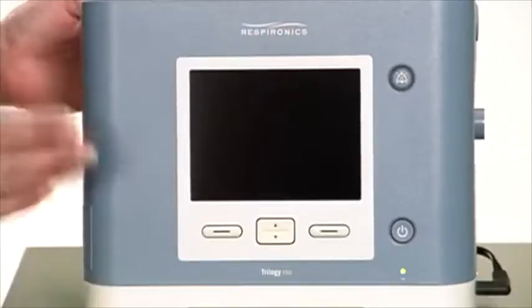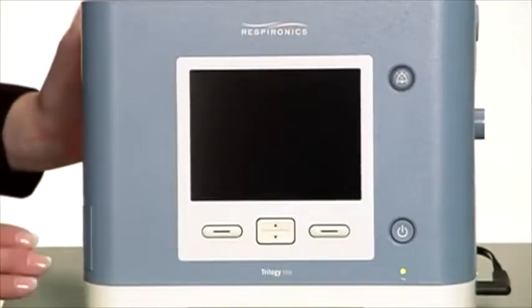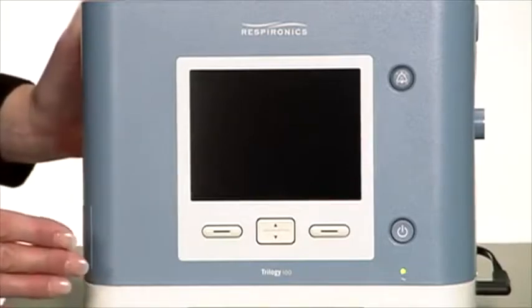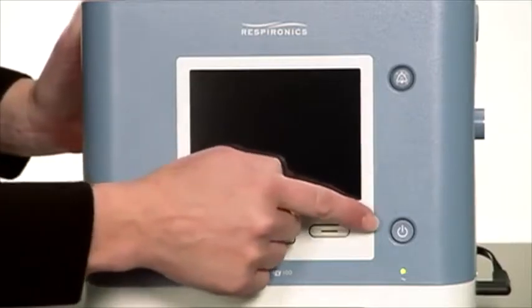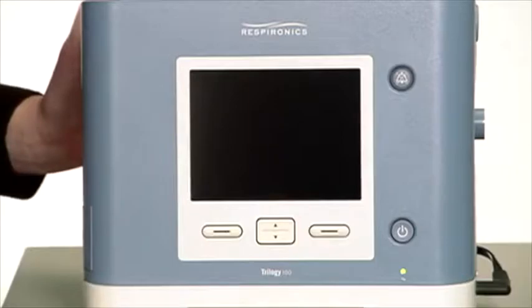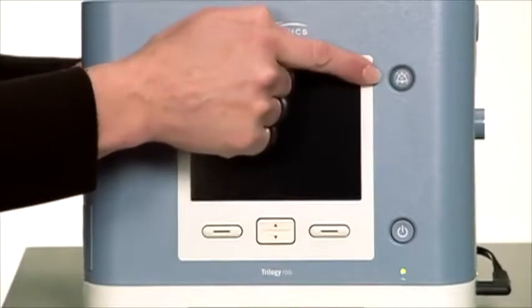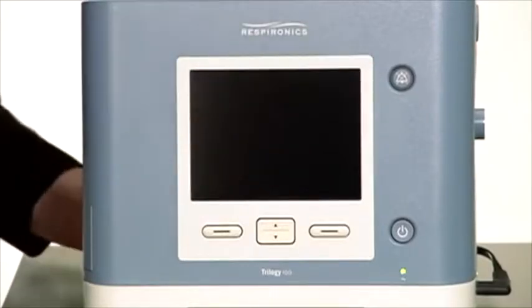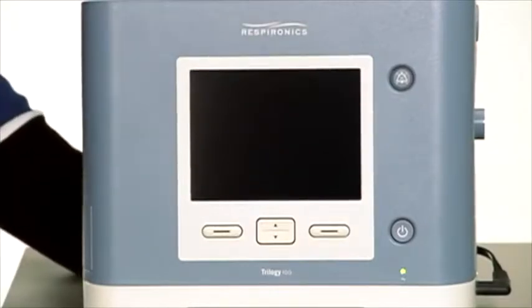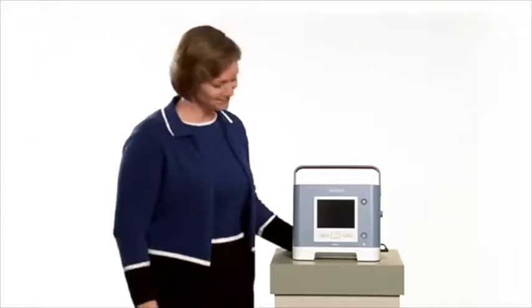Here on the front, you see control buttons, visual indicators, and the display screen. The Start-Stop button at the bottom starts and stops the flow of air, which is how you begin or end therapy. Above it is an audio pause button, which temporarily silences the audio portion of an alarm. If the cause of the alarm is not corrected, it will sound again in 1 minute.